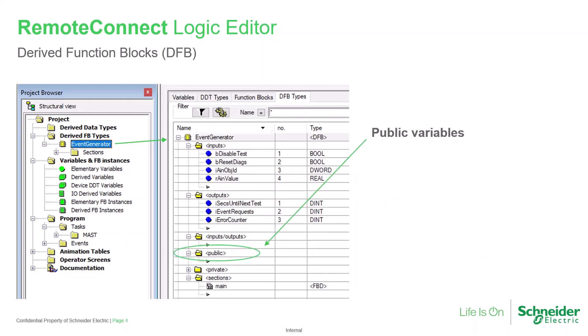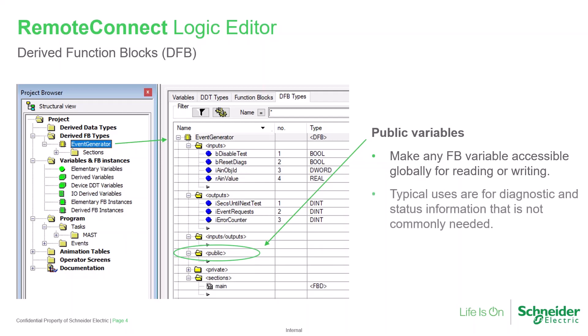A DFB may also include public variables. These will be available globally, anywhere within the entire application. A common use for a public variable is to share diagnostic or status information with the rest of the application. For example, a motor starts counter.